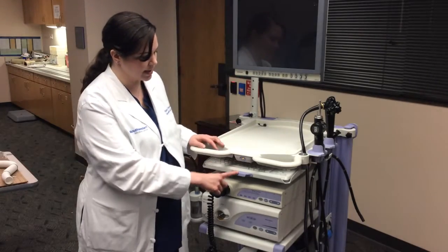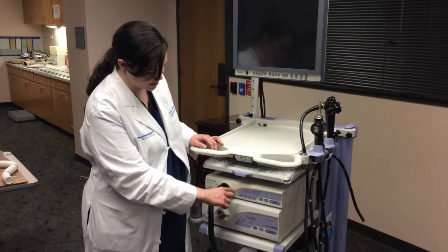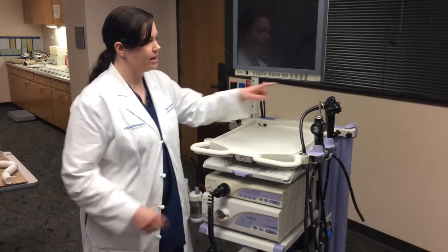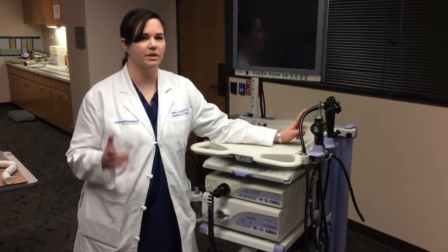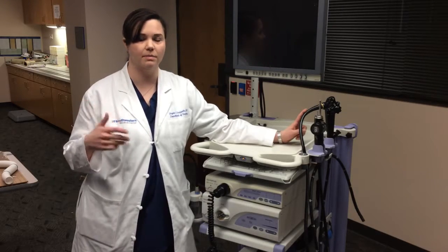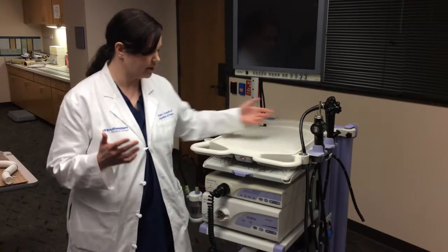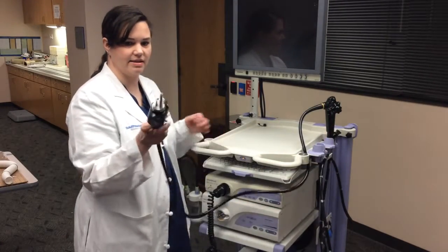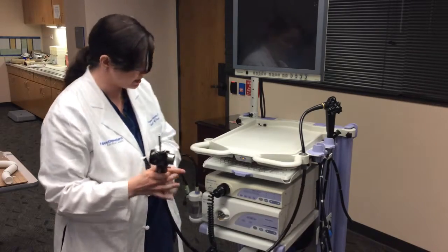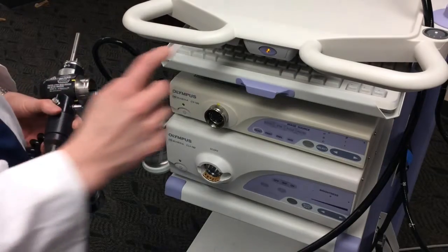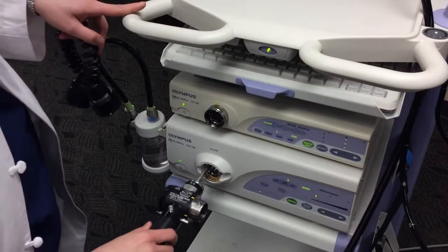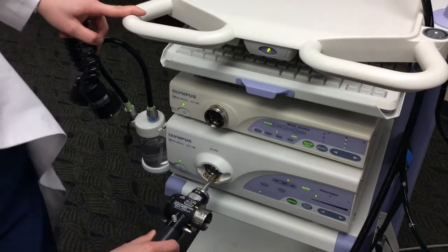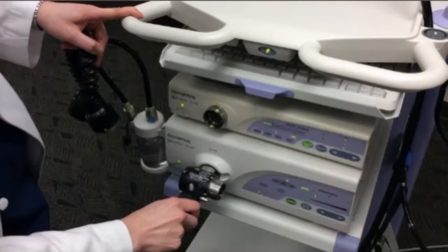It's got a screen, it's got a keyboard, it's got light source right here and video right here. This is our colonoscope. We're going to set up the colonoscope because it's a little more tricky than the upper endoscopy, but it's the same principle. So what you're going to do is take your scope. It has this right here with the pins in it. Pins go right here. You can look inside and see how it aligns. There's a big pin that goes on top and a little pin that goes on bottom, and it just slides in and plugs in.